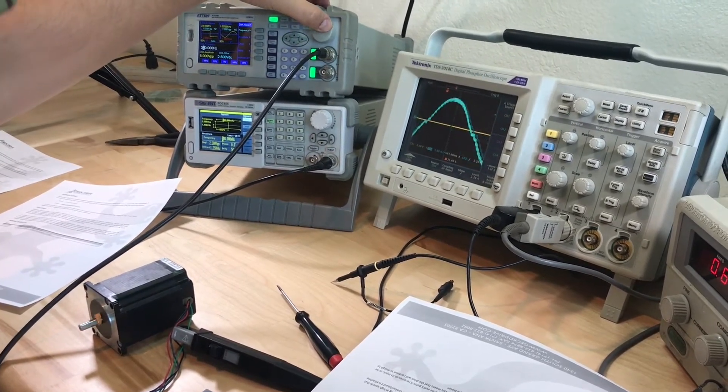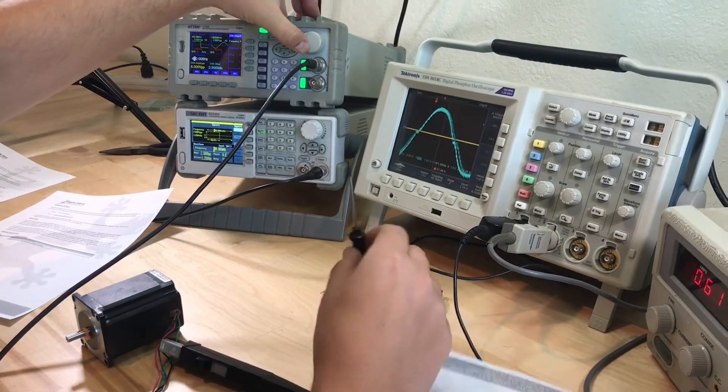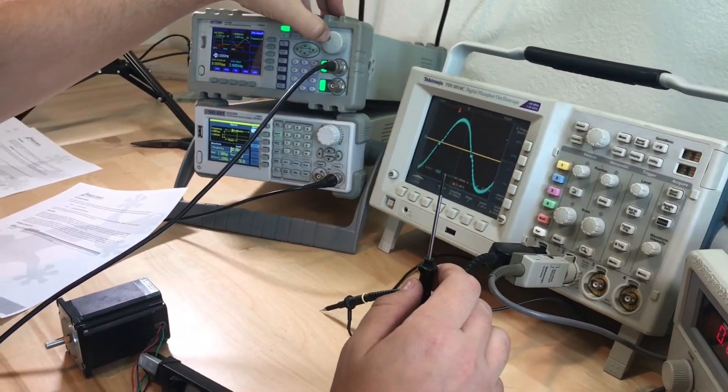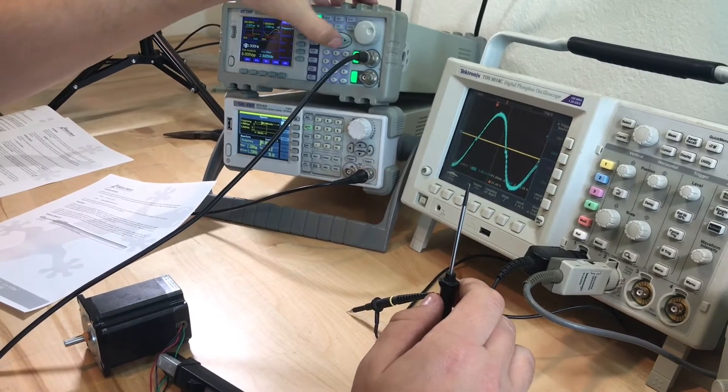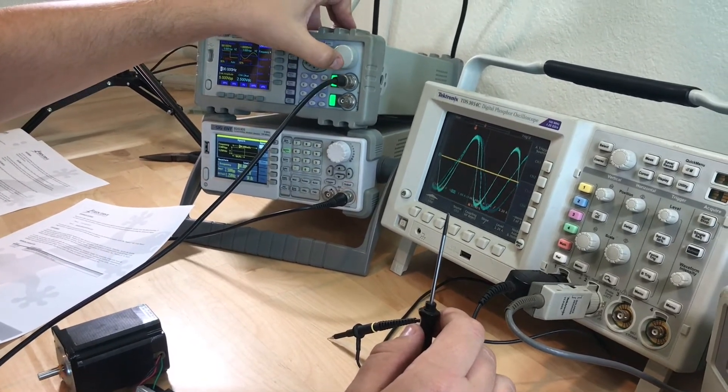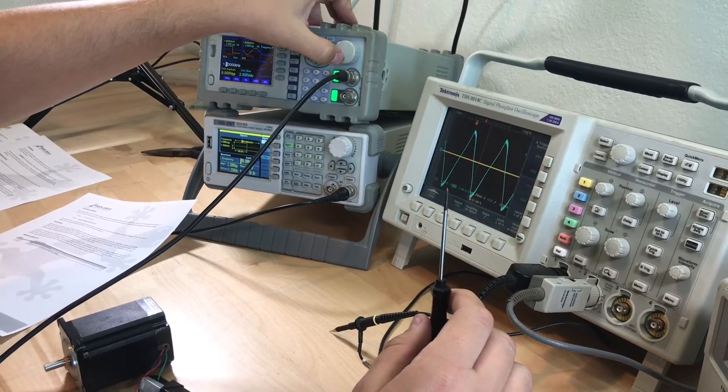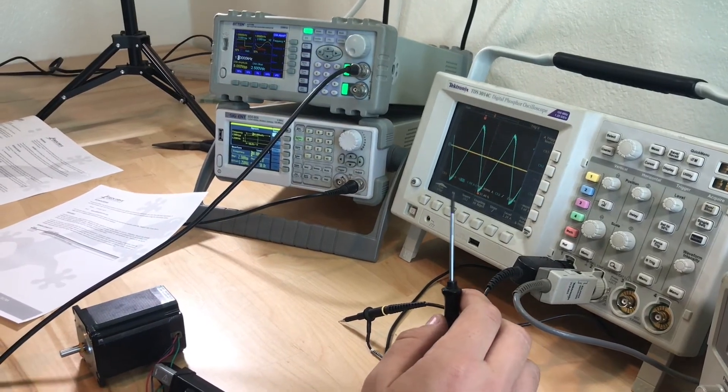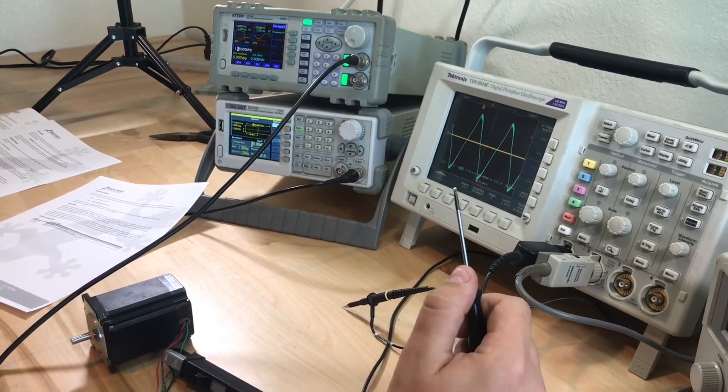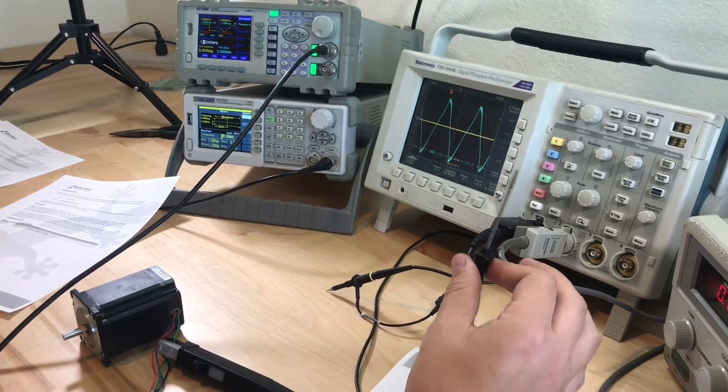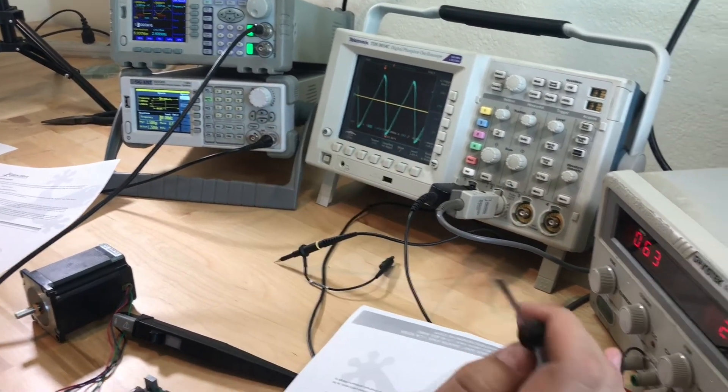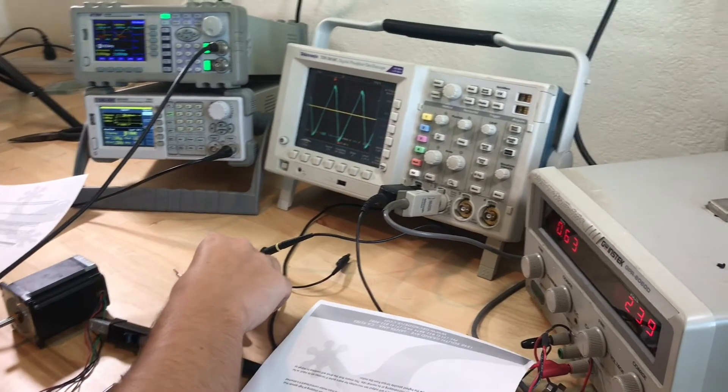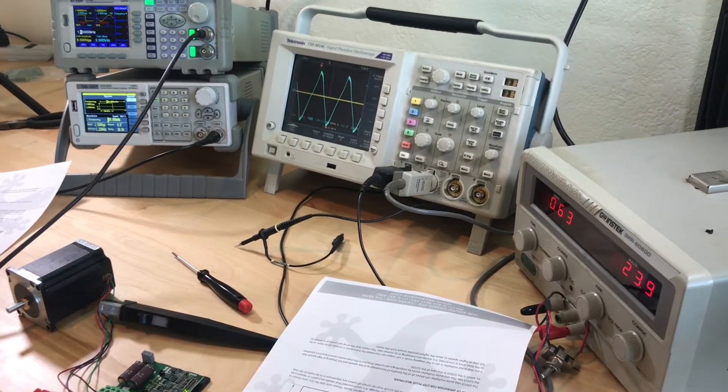And then we bring it back up. We accelerate through, that's a first order resonance right there. And then we get back to one kilohertz, five revolutions per second. The number is going to be 200 pulses per revolution at full step. And that is the quickest way of getting your drive up and running.